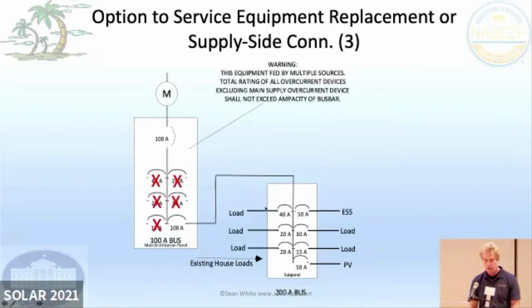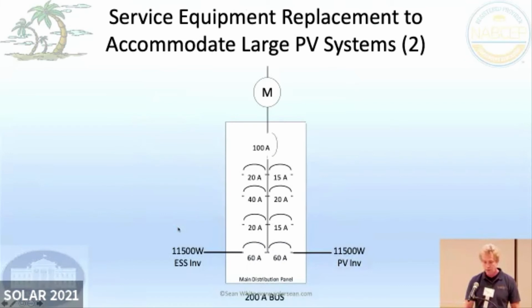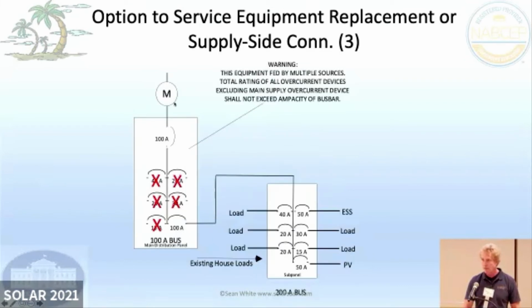And then some people call this one the Hawaiian tie-in. You've come up to a house and maybe it's like an all-in-one meter main, where even sometimes the meter is built into the panel board and it's rated for 100 amps. And you want to add a 200 amp panel board, but it's like, well, shoot, what am I going to do? Pull out the meter and tear the wall down? It's just going to be very complicated. And you want to be able to power all your loads with AC coupling and do all this great stuff. And so what people are doing is they're just kind of in a way bypassing this main service panel. So they have a 100 amp breaker here and a 100 amp breaker there.